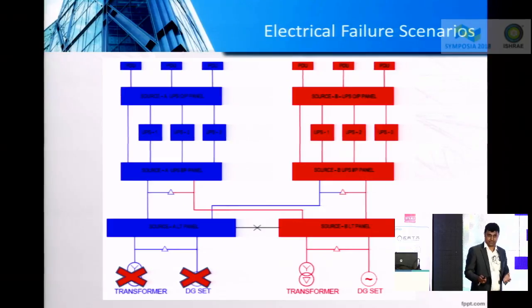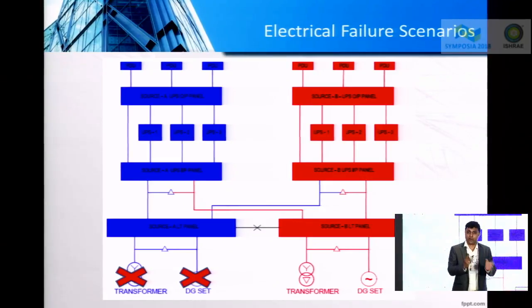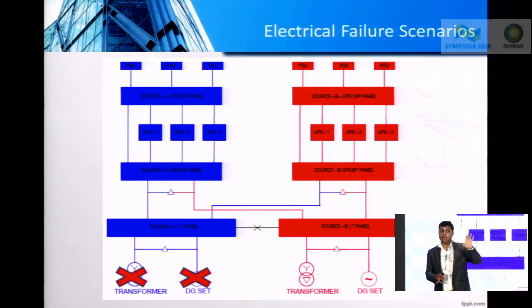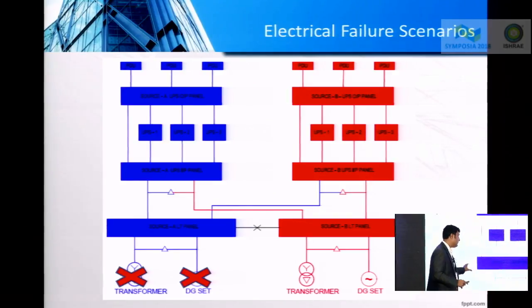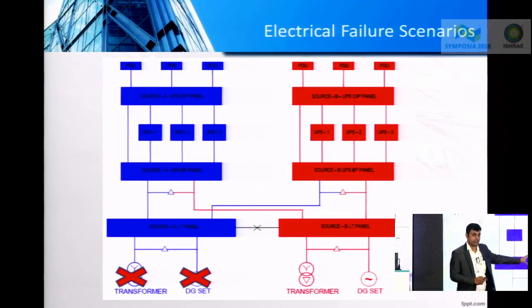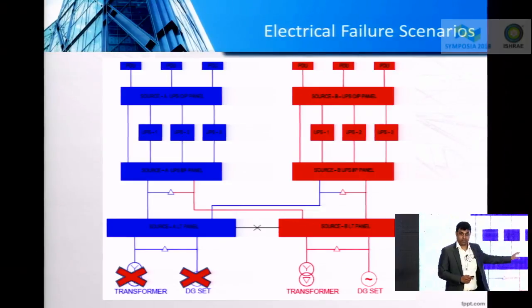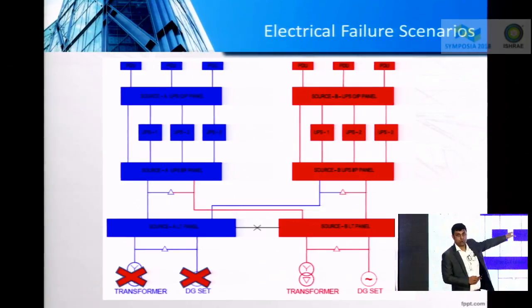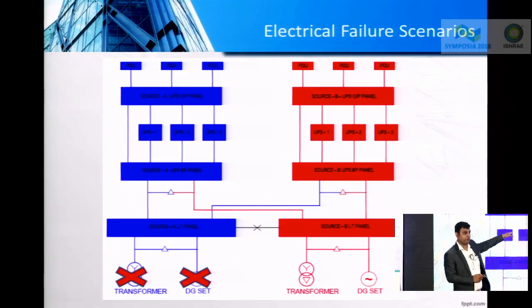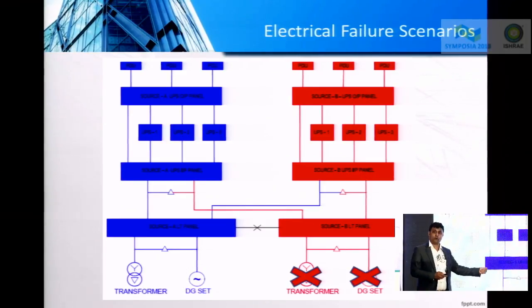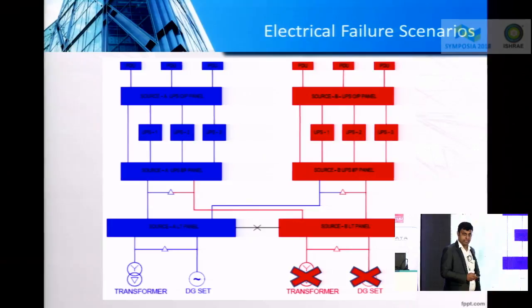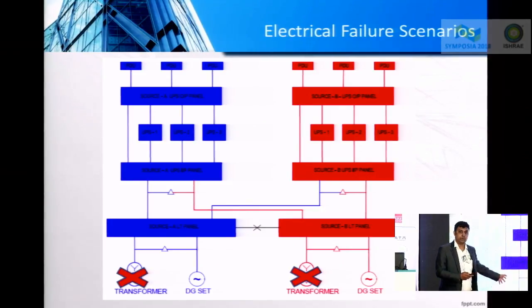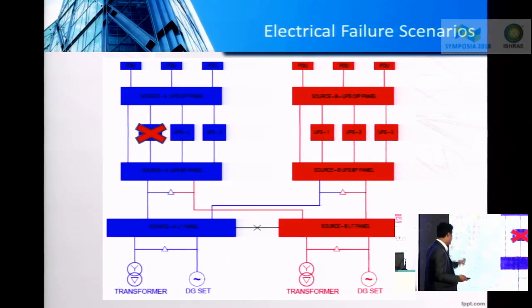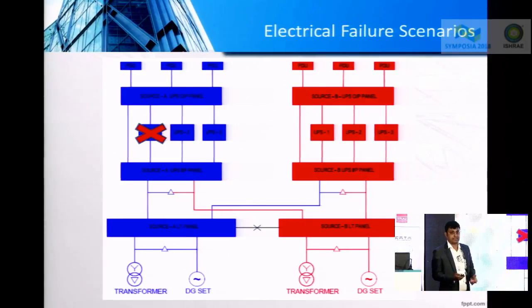There are many cases and practical scenarios when you try to fail a utility supply and you are expecting a changeover to DG, but the DG fails to start. This could result in complete source A failure. Here we are expecting that the source B transformer takes care of the entire load and there is absolutely no break at the output supply of UPS. I can do the same for the source B system. I can fail the complete utility supply. We can fail the UPS, one of the UPS.